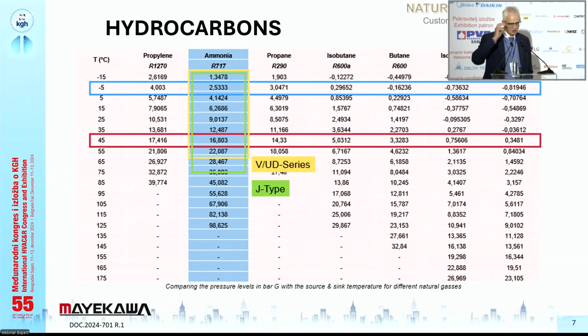And if you look to the hydrocarbons, there is the whole list there, starting with propylene up to pentane. You will see that the pressures under the refrigerant in the column are getting much lower. So for operating at 22 bar, it's 55 degrees with ammonia, you come only at a pressure of around 1 bar for pentane, and all in between are following.